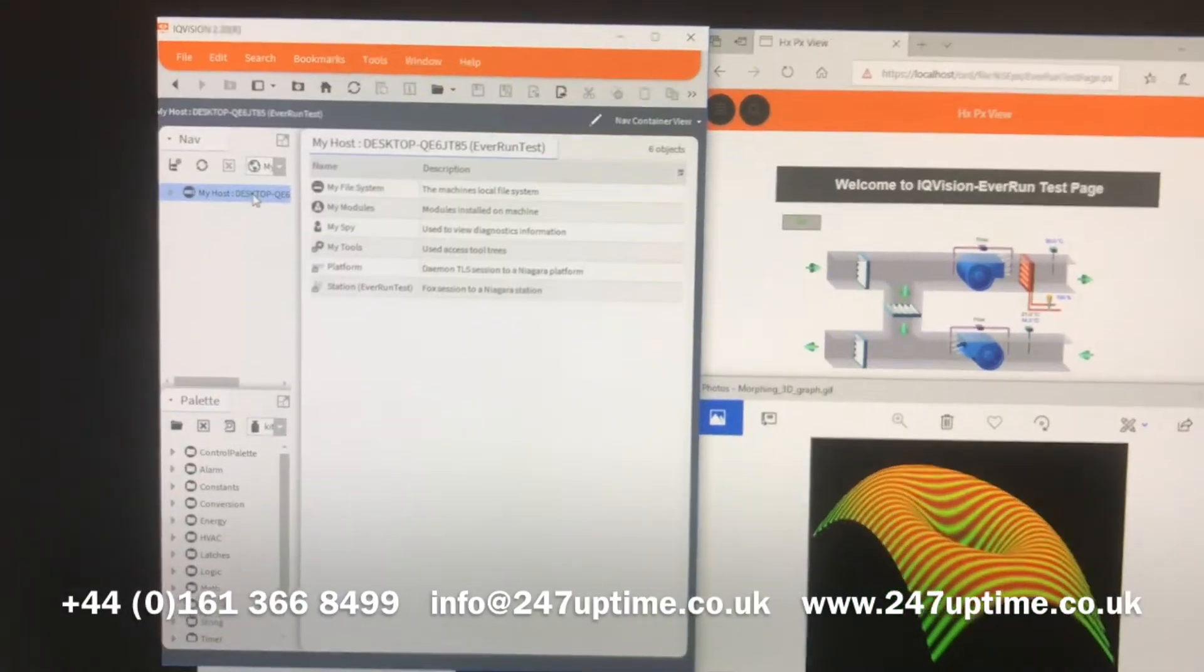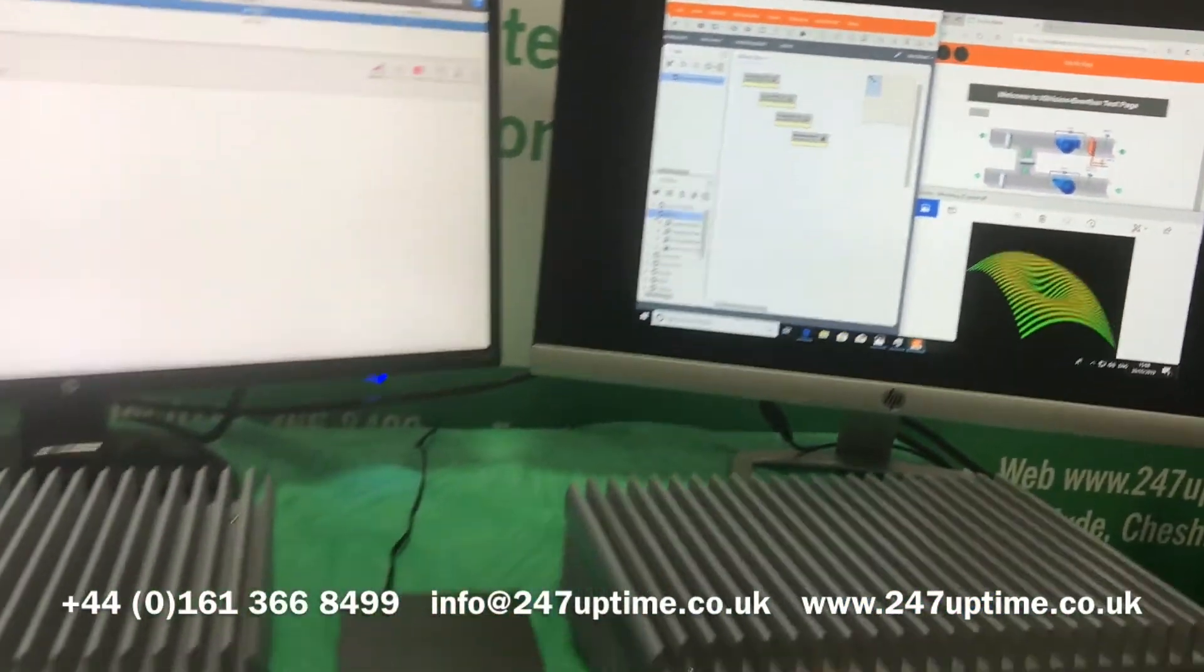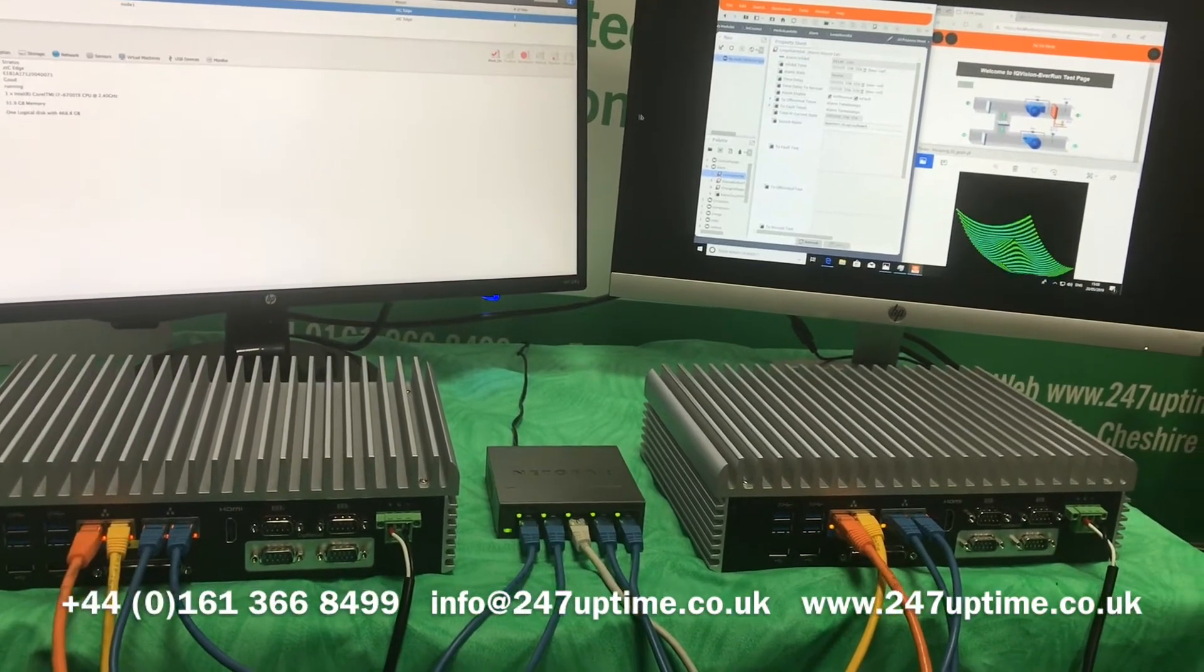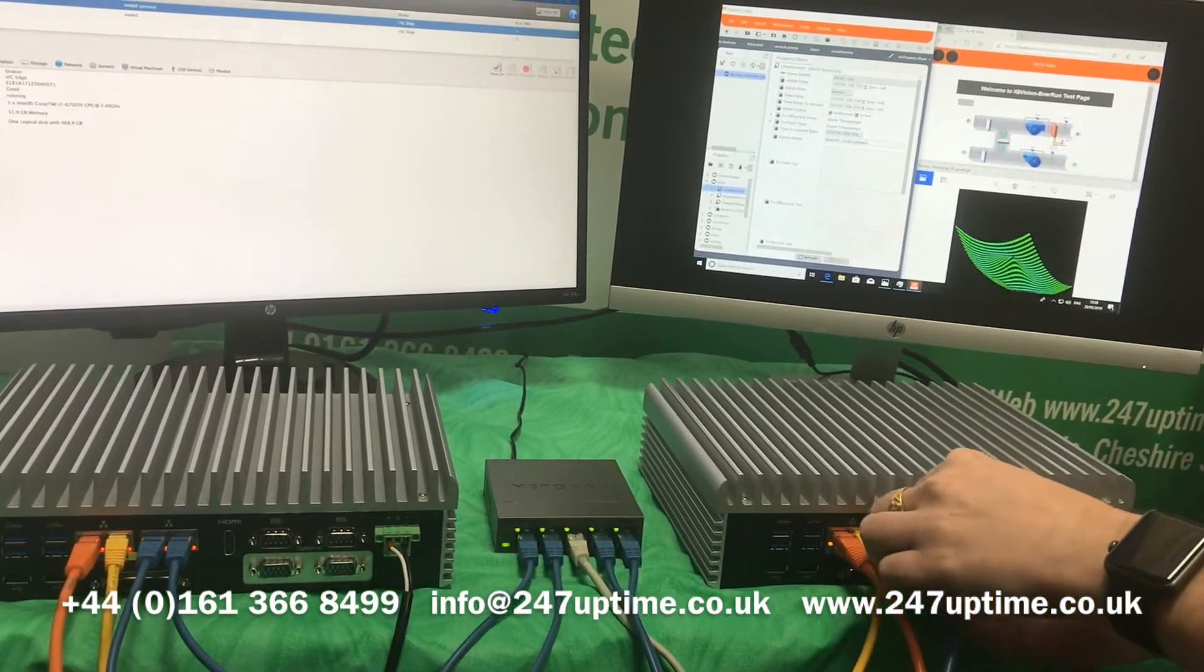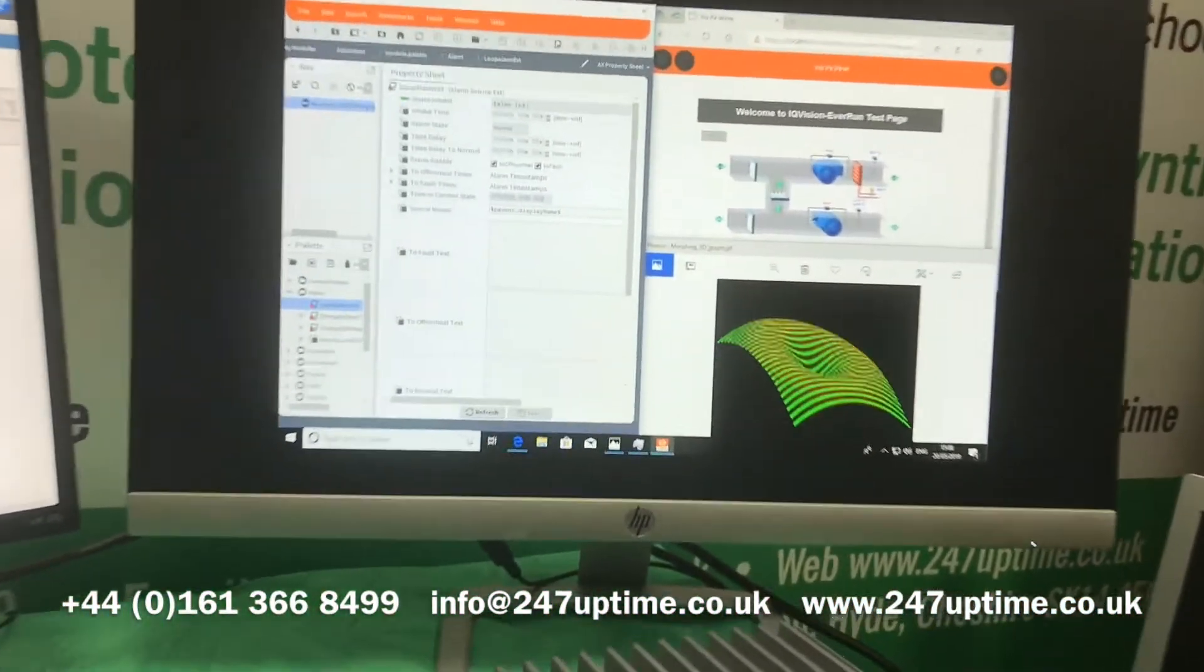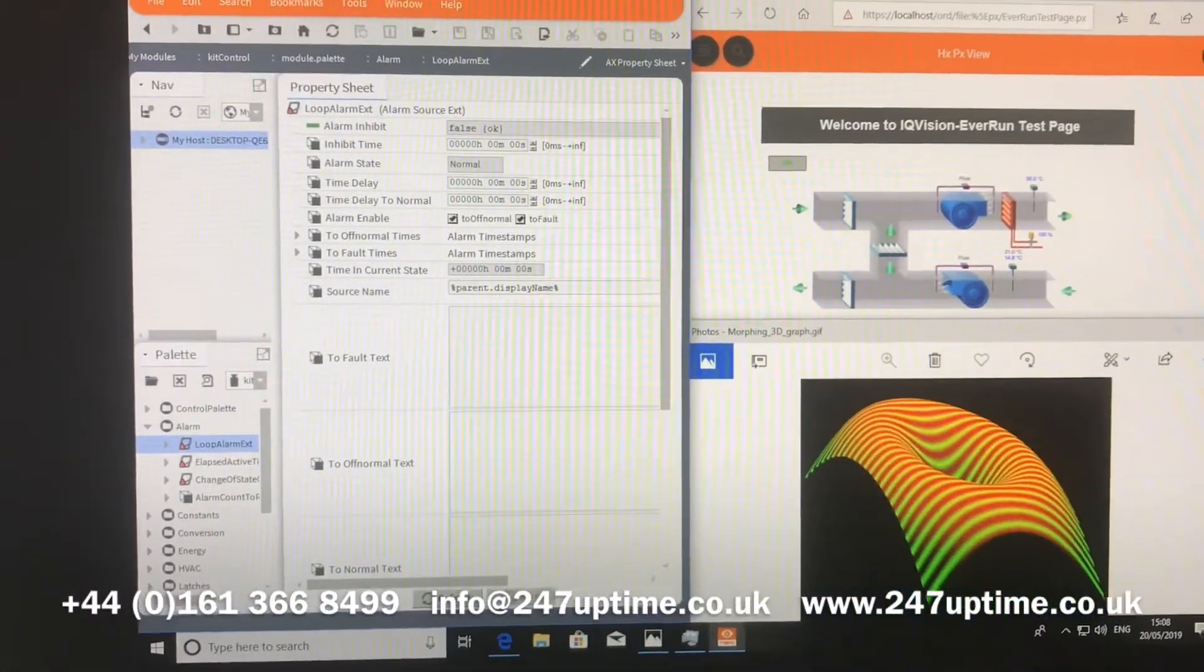On the left, we've got the Niagara 4 control panel. As you can see, Tim can change some tabs so that it's actually a live environment, albeit in this lab. We will now do something you would never do in normal practice, and we will pull the network cables from the system. The production network cables on the right server are now completely disconnected, but you will notice that the applications have carried on through that failure with absolutely zero downtime.